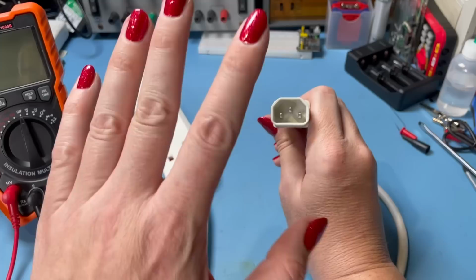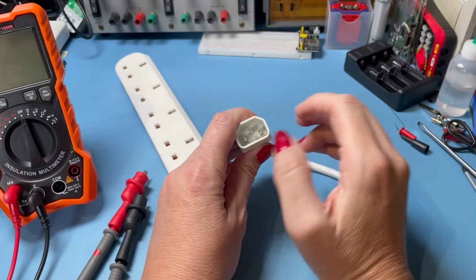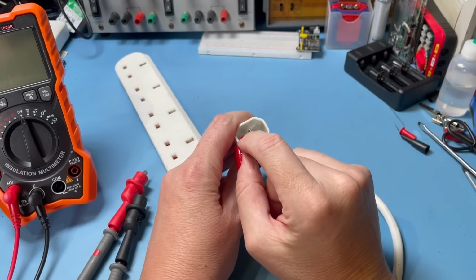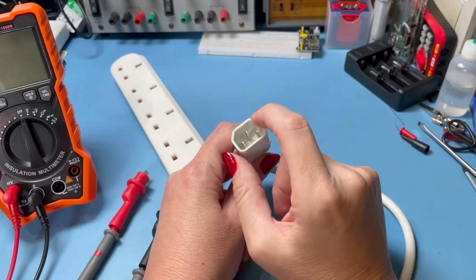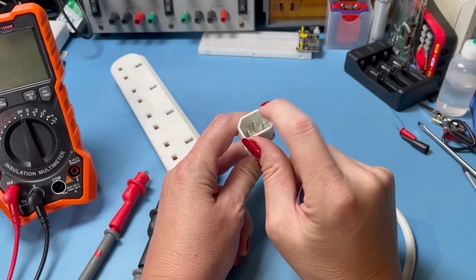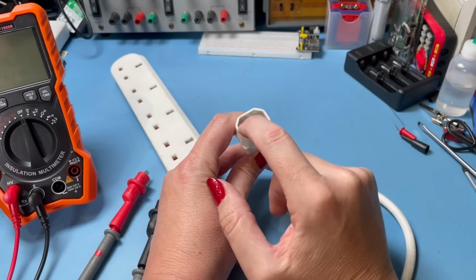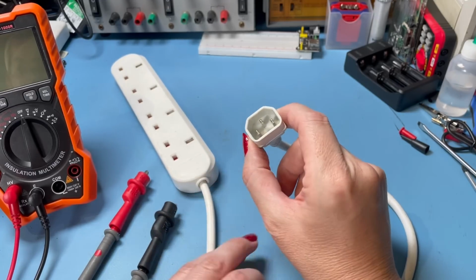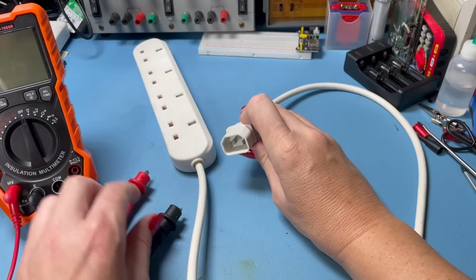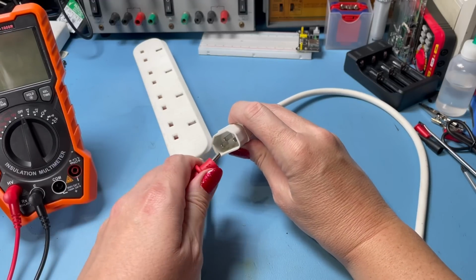Now, remember, I'm no electrician. I'm just going on instinct here and best practice that I know of. So we're going to test between live and earth, neutral and earth, and live and neutral. And we should get comparable readings, really. So we're going to see. First of all, I'm going to hook it up live to earth.